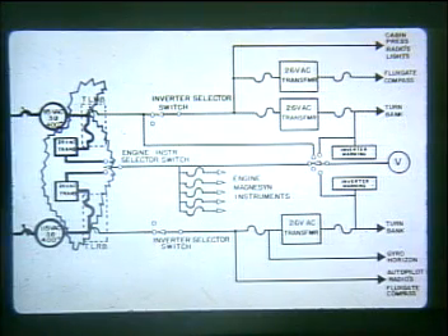26-volt AC power is required to operate certain engine and heater instrumentation. This power is taken from the inverters through two 26-volt AC step-down transformers called engine instrument transformers. The transformers are always associated with an individual inverter, so they are referred to as the upper or lower engine instrument transformer. Power for these transformers is taken off the inverters prior to the phase breakers and are each protected by a fuse, referred to as the upper or lower engine instrument transformer fuse.